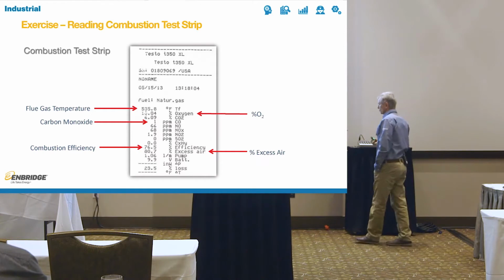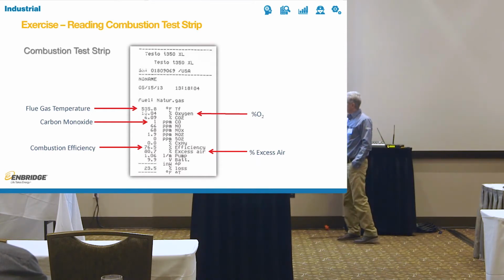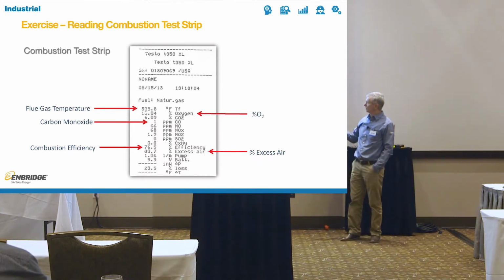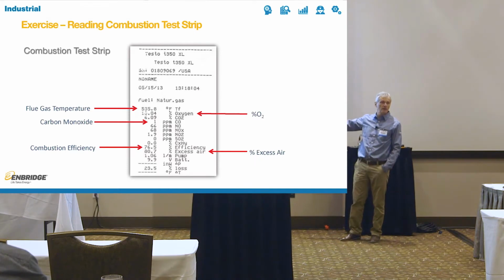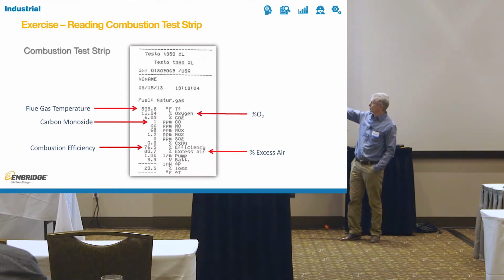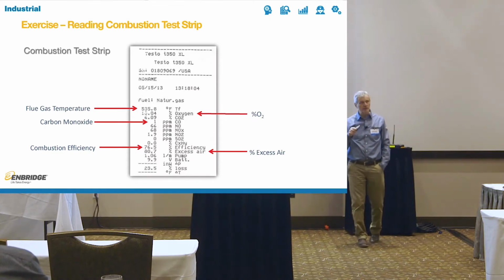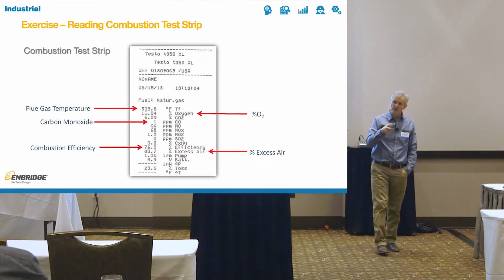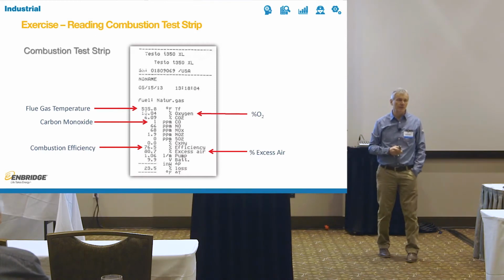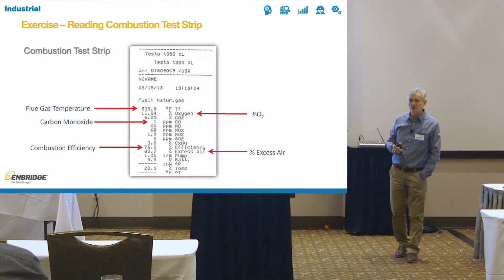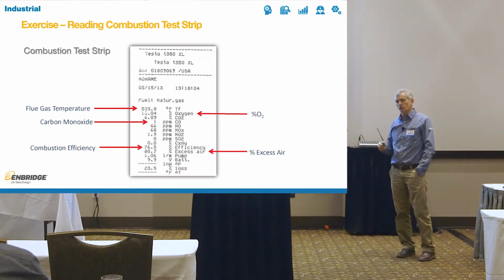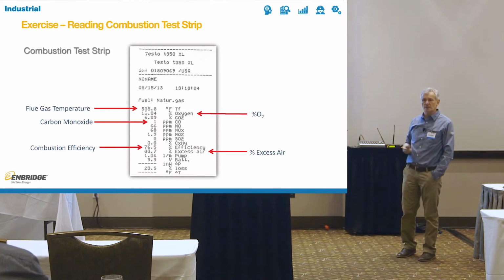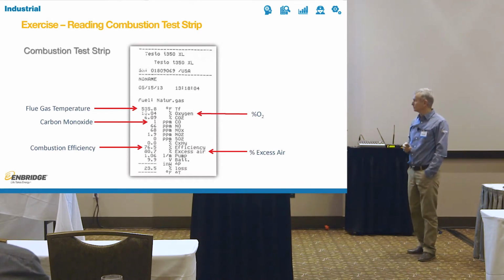So when we do a project for you, when we want to evaluate how much savings we can get out of the economizer, for example, these are invaluable for us because then we put in the raw numbers for the temperatures, oxygen, all these gases, and we calculate exactly what your efficiency is, and then we can calculate exactly what the savings are going to be. We've done that for years. We're pretty good. We can do a quick calculation and give you plus or minus 2% savings levels.